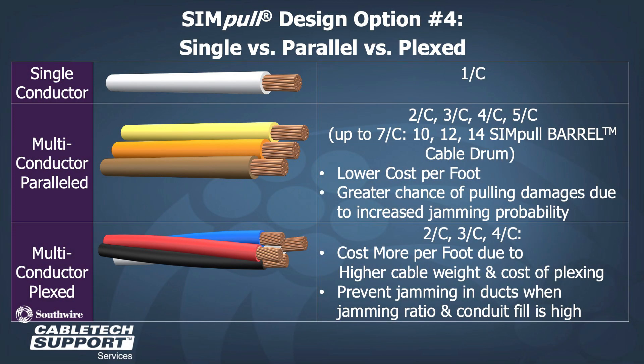Our fourth design option is the cable assembly. Where multiple conductors are being installed, Southwire offers parallel and plexed assemblies. For parallel assemblies, we have two to seven conductor options, which is lower cost per foot compared to plexing; however, when pulling into conduit, it does have a greater chance of pulling damage due to increased probability of jamming. For plexed assemblies, we have two to four conductor options, and this design will prevent jamming when the jamming ratio and conduit fill is high.